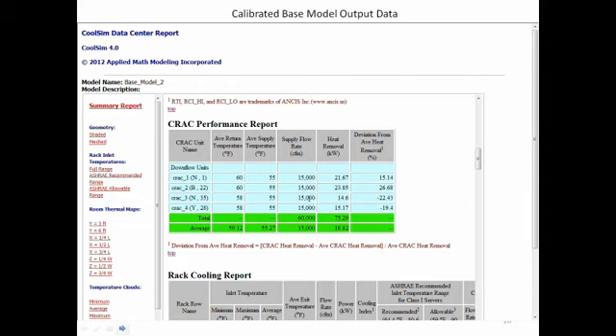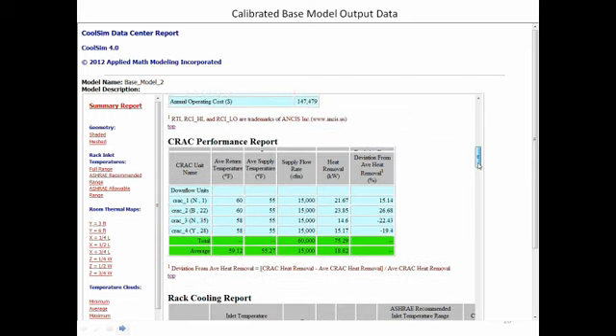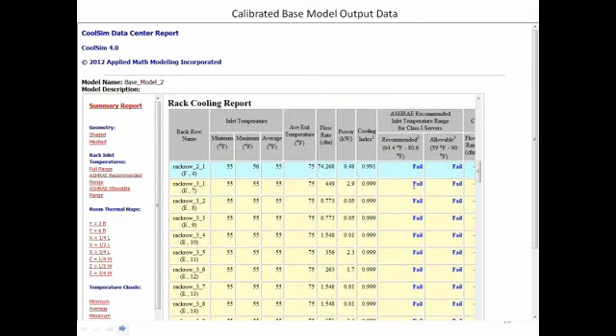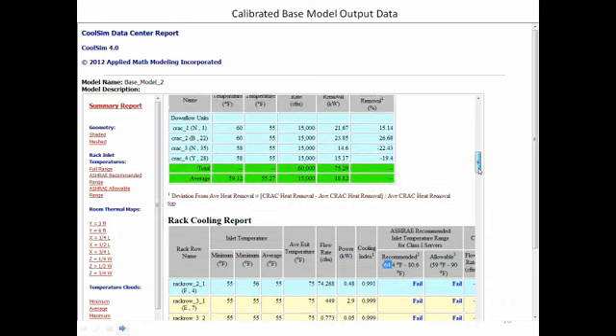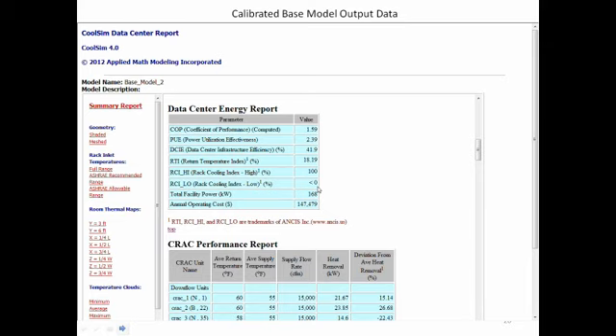By the way, the maintenance cost on this unit is going to be high too because it's cycling on and off. Can't figure out whether it should be on or off. It's underloaded. It's running way below its design point. They don't work well there, so maintenance is going to be high. Reliability is going to be impacted. And it's failing the ASHRAE spec with respect to cooling. It's too cold. The specification says 64.4. And we're running this thing down to 55, so we're below the spec. And that's why back in the energy report, we have it less than 0. Actually, the calculation shows it as a negative number. We decided the best thing to do here is just say, yeah, it's 0 or less. Yeah. Forget about it. A couple other things we've done in CoolSim 4, which are kind of nice.